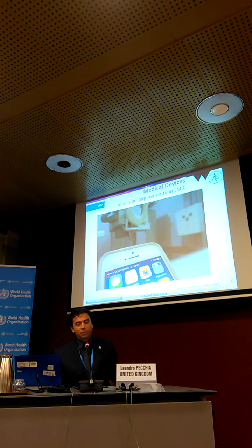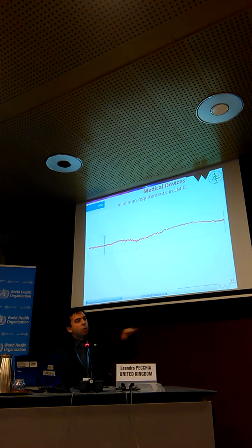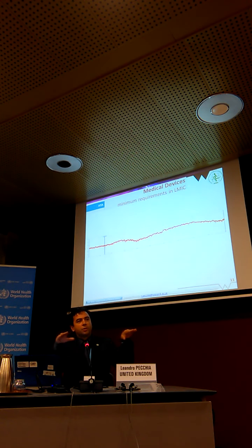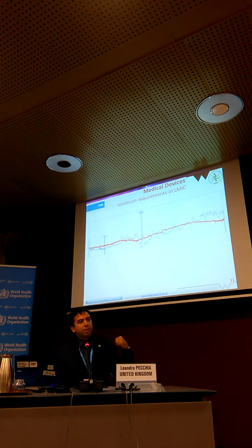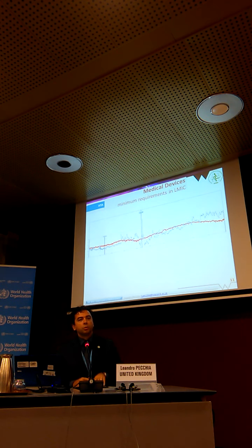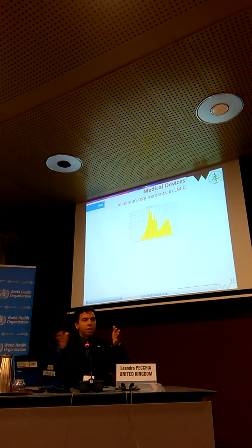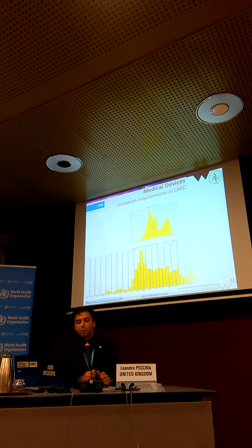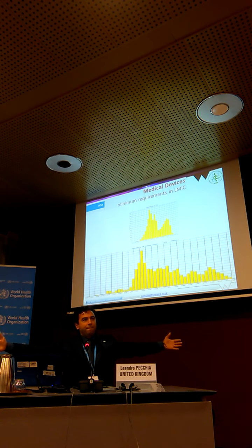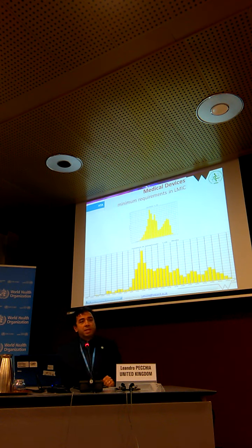This is the trend of voltage — a measurement from my house in Rome shows voltage is stable, slightly up during the night, as expected. This is the same measurement in a dormitory in Benin: you see more or less the same trend, apart from the fact that suddenly the voltage jumps to 300 volts. On a histogram, voltage in Rome is around 220 plus or minus five volts; on the same scale in Benin, the range is twice as wide.